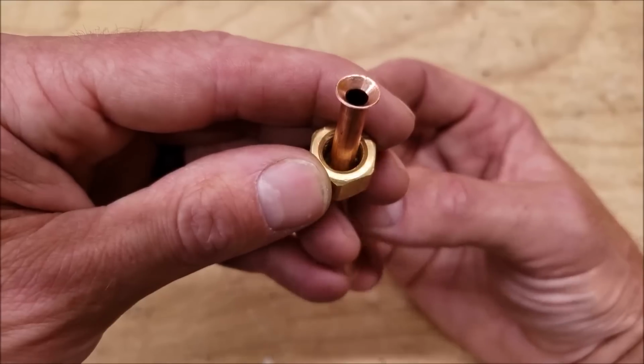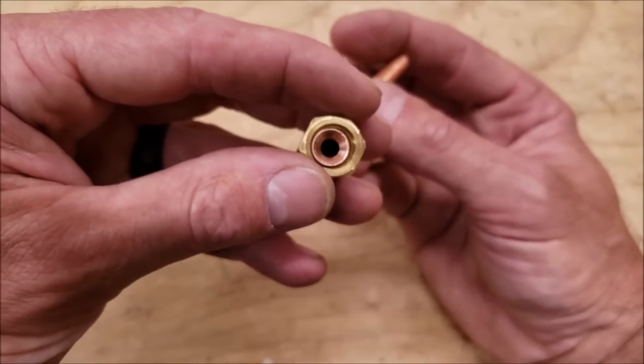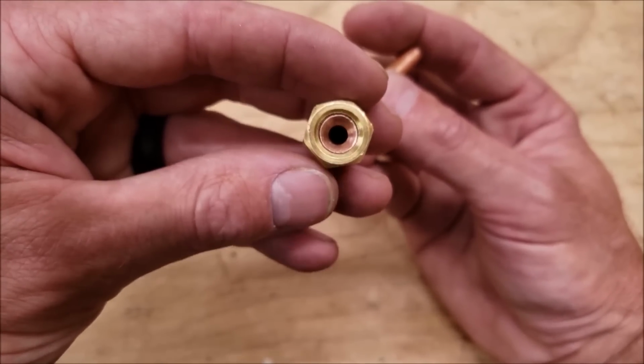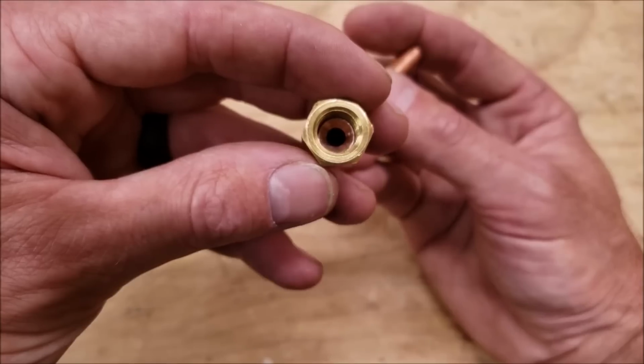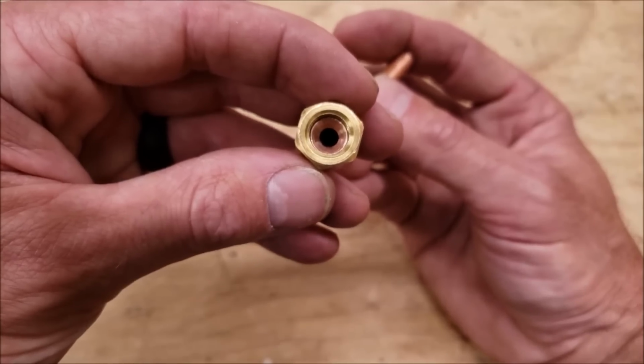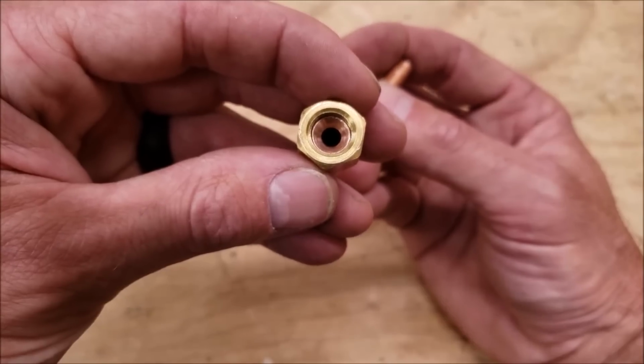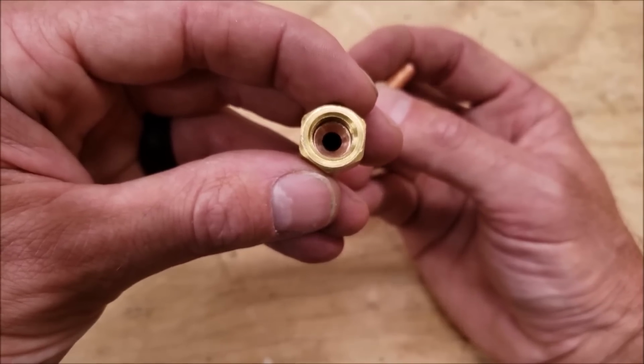And you want to make sure that the flare that's drawn out is taking up the majority of the inside of the flare nut. And speaking of the flare nut, by the way, you want to make sure to use the manufacturer's flare nut, not necessarily just the flare nut that came with the line set, because it might be too small. It might be a plumbing flare instead of something that's rated for high pressure, from the manufacturer, and rated for the torque values that you're going to tighten it down to. But anyway, you slide your nut over the flare, and that's good.